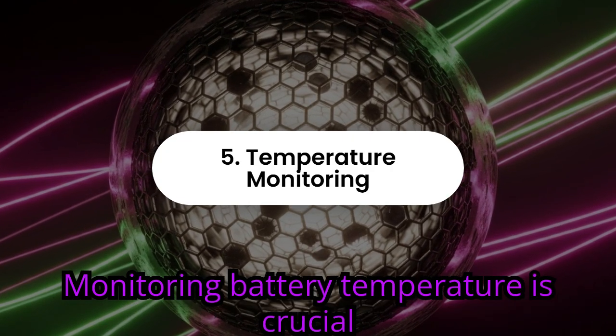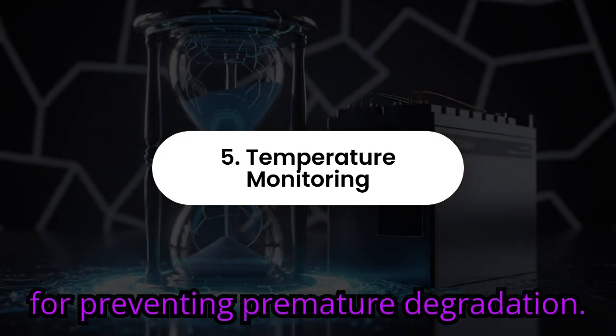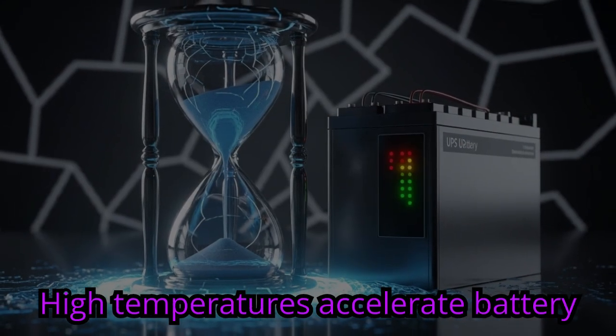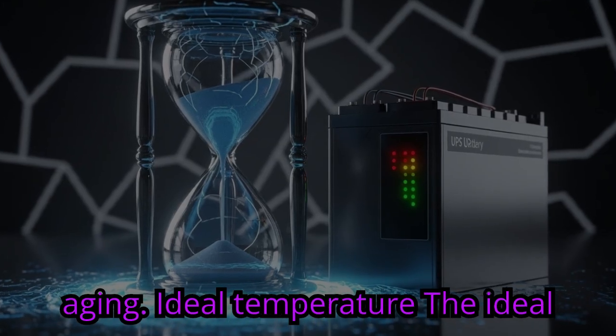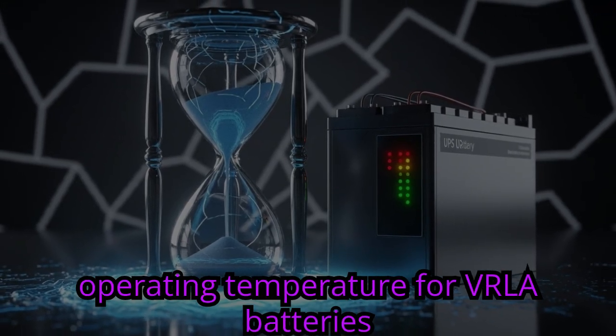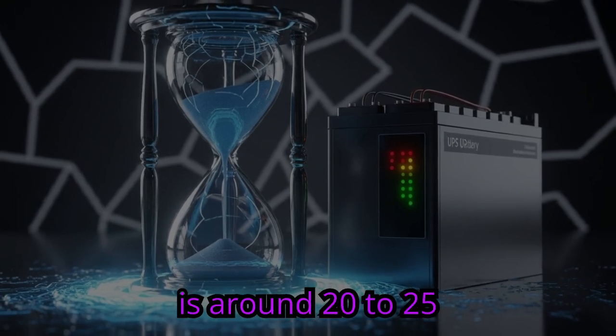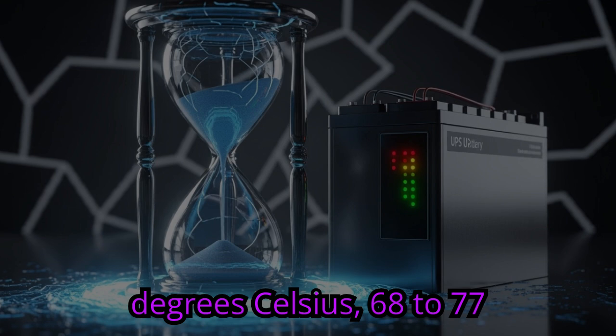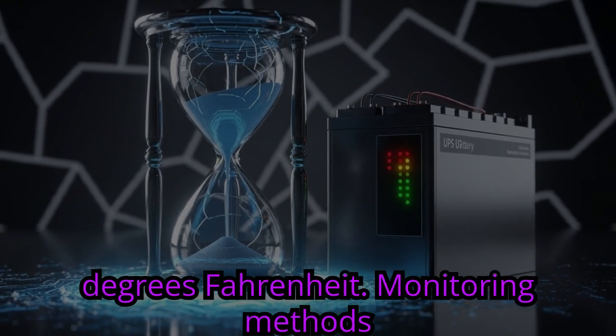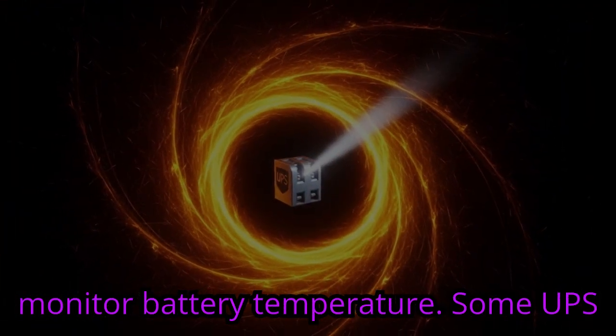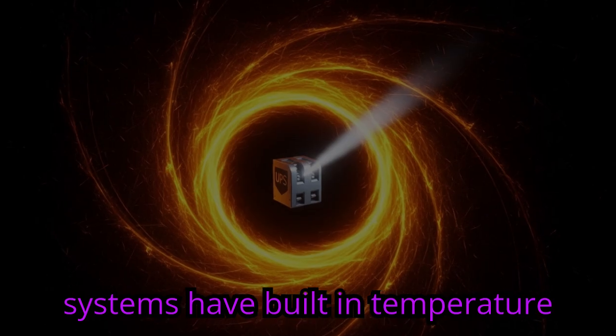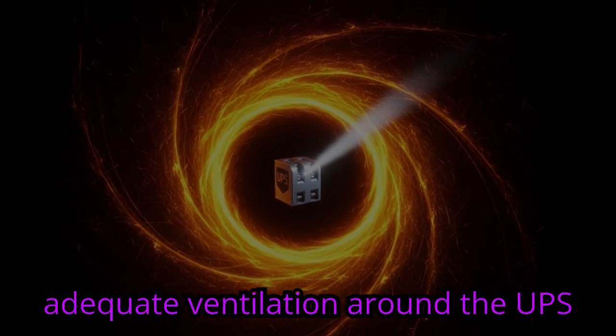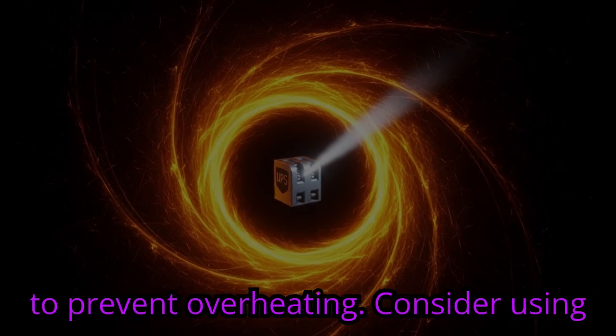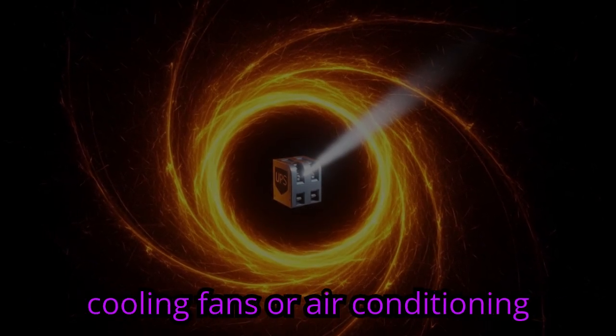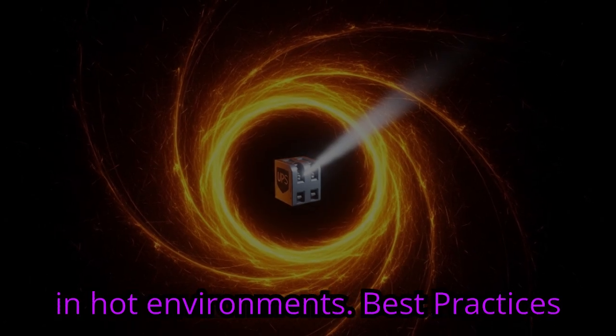5. Temperature monitoring. Monitoring battery temperature is crucial for preventing premature degradation. High temperatures accelerate battery aging. Ideal temperature. The ideal operating temperature for VRLA batteries is around 20–25 degrees Celsius, 68–77 degrees Fahrenheit. Monitoring methods. Use temperature sensors to continuously monitor battery temperature. Some UPS systems have built-in temperature monitoring capabilities. Cooling. Ensure adequate ventilation around the UPS to prevent overheating. Consider using cooling fans or air conditioning in hot environments.